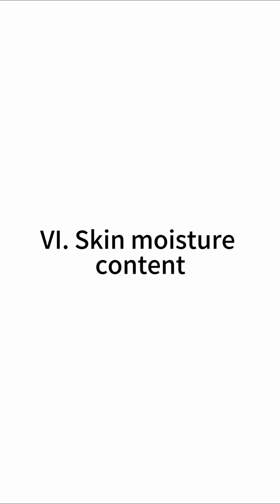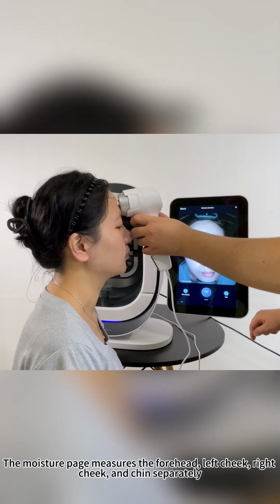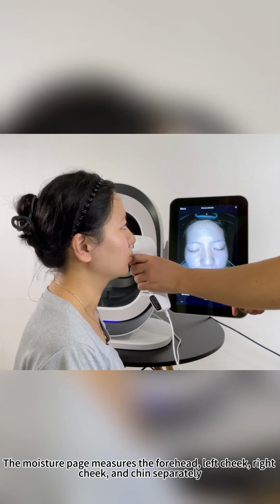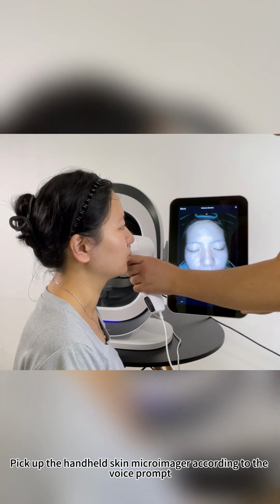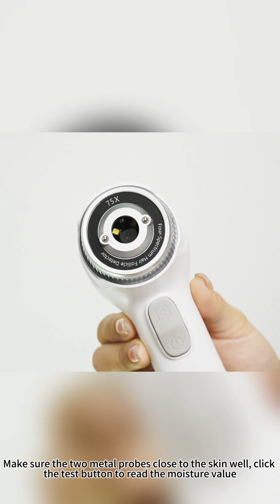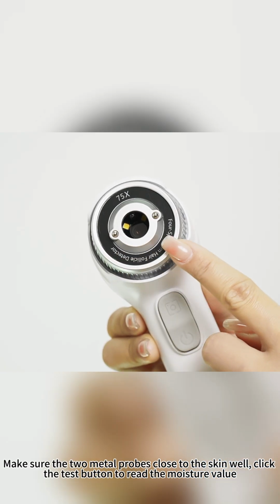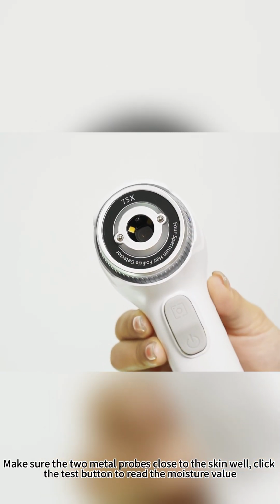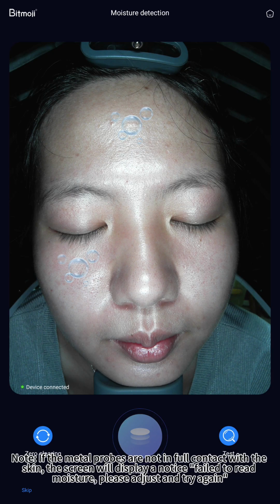6. Skin Moisture Content. The moisture page measures the forehead, left cheek, right cheek, and chin separately. Pick up the handheld skin microimager according to the voice prompt. Make sure the 2 metal probes are in close contact with the skin. Click the Test button to read the moisture value. Note, if the metal probes are not in full contact with the skin, the screen will display a notice: Failed to read moisture. Please adjust and try again.